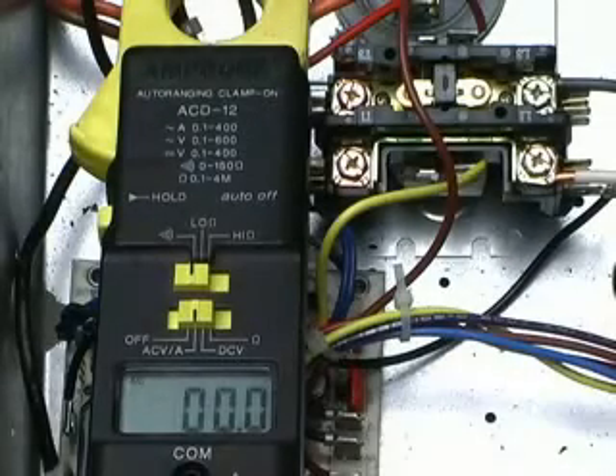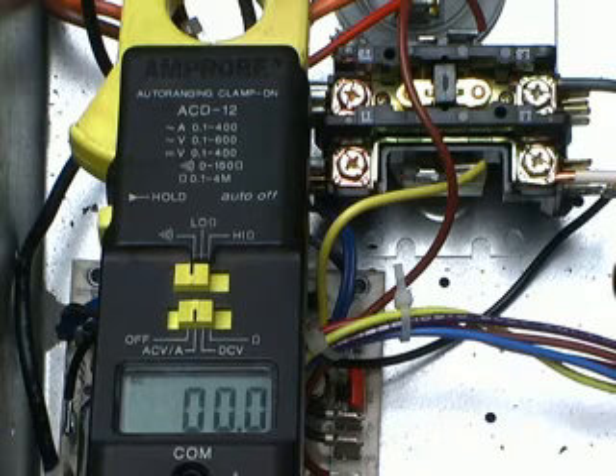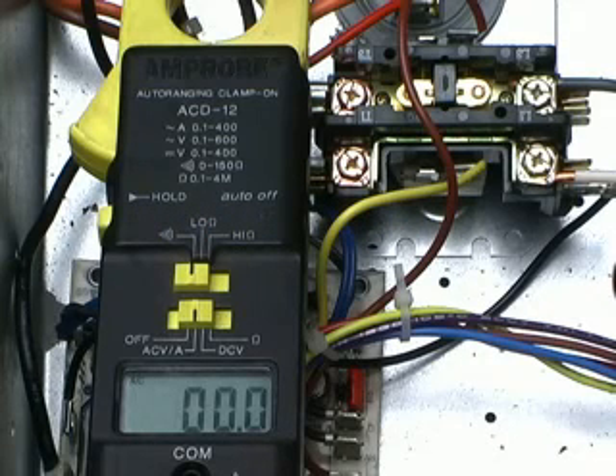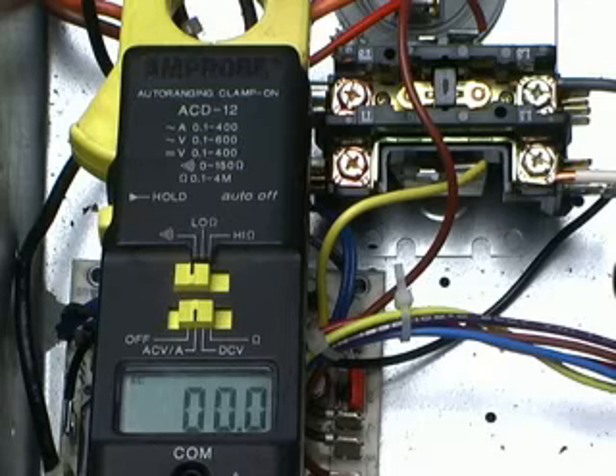Now on this particular unit, when you're checking the compressor, if it's trying to run and won't run, I'm just going to use the clamp ammeter to show you that it pulls locked rotor amps or something near locked rotor amps. Then you have to decide if the compressor is actually locked up, or if there's an electrical problem somewhere that's not allowing it to get the amount of torque it's supposed to get. So when the contactor pulls in, you'll see something like this.